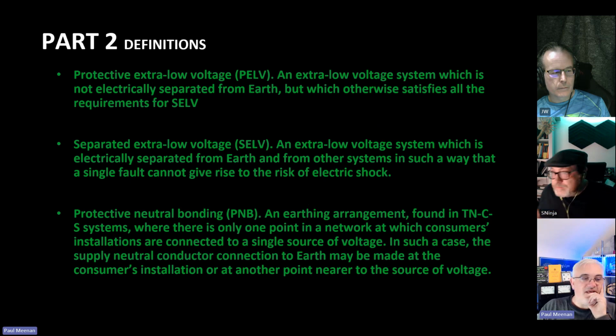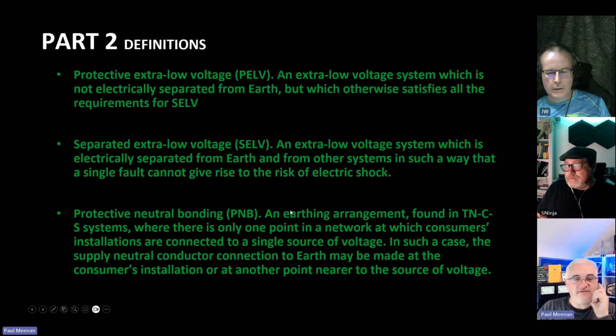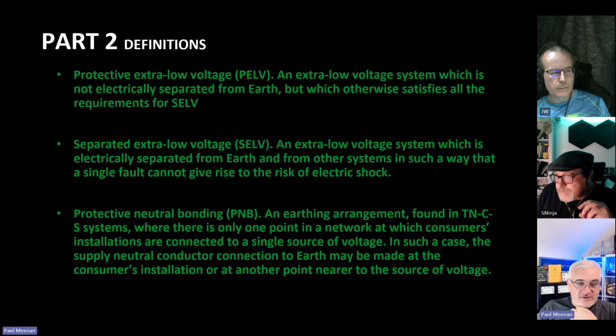So new one, PNB, an earthing arrangement found in TNCS. It's kind of a cousin to PME, where there is only one point in a network at which consumers' installations are connected to a single source of voltage. In such a case, a supply neutral connection to earth may be made at the consumer's installation or another point.